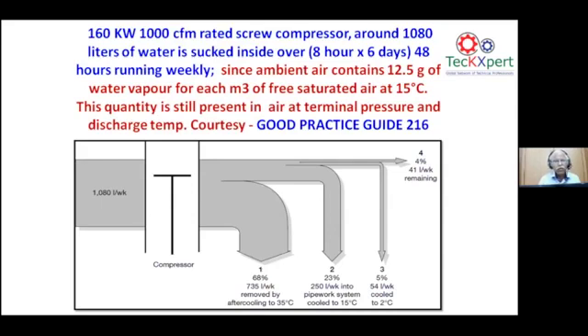So definitely almost 68% the post air cooler is supposed to function, and 23% has to be cooled by the pipelines, especially on the receivers. It has to get cooled by the receiver, and the receiver is auto drained out through the level sensing drain valves. Then only it is getting cooled, and the water is removed. 54 liters, 5% is removed on the pipelines up to the tail end process.